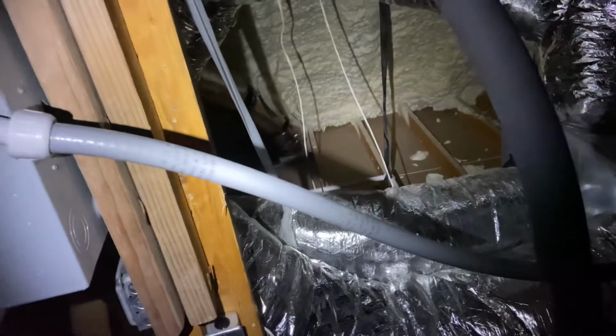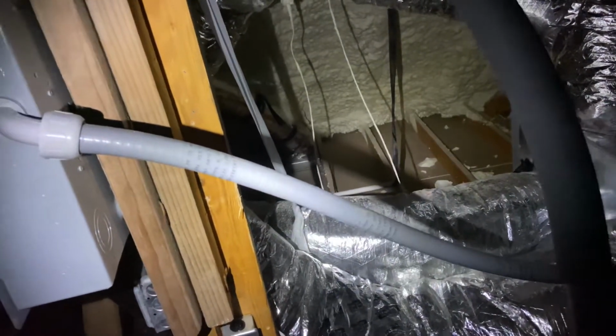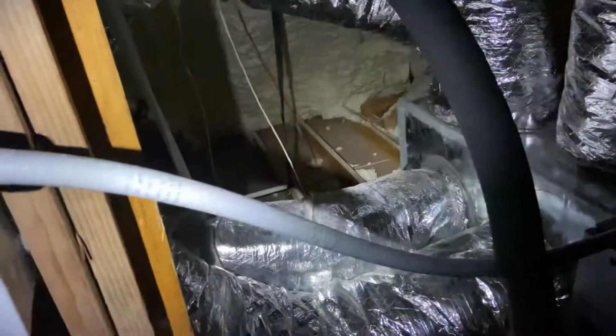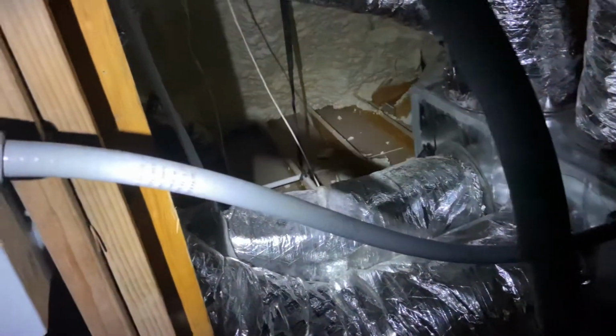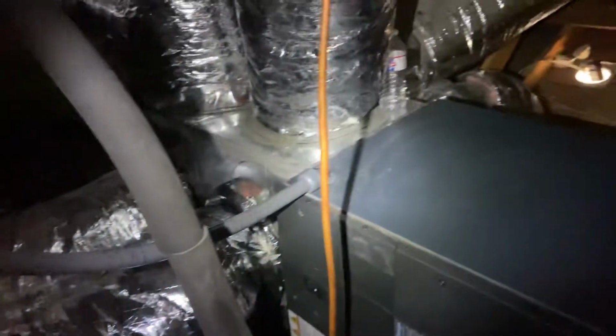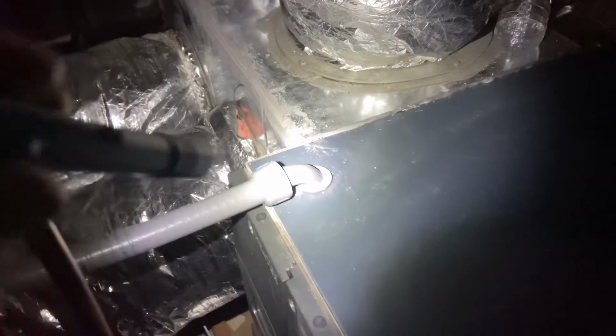If you're running multiple circuits in one conduit, right, you do not have to run more than one equipment grounding conductor. They can share. It doesn't matter, as long as you size it for the largest circuit. So in my case, either way, it's number 10, so that's what I ran. And in case of here, just so you're not caught off guard if you do the same thing, I had to drill that hole into that case. There are predefined little dimples around this that they have provision to run conduit into, depending upon your installation. So this is where I needed to do it.